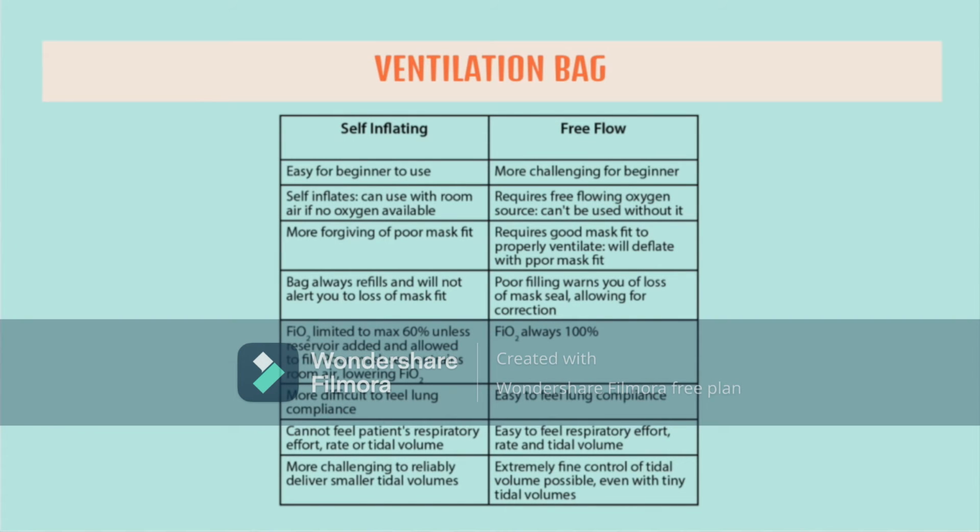For the ventilation bag, we have two kinds. First is the self-inflating. It is easy for a beginner to use. It self-inflates, which means it can be used with room air if no oxygen is available. It is more forgiving of poor mask fit. The bag always refills and will not alert you to loss of mask fit.